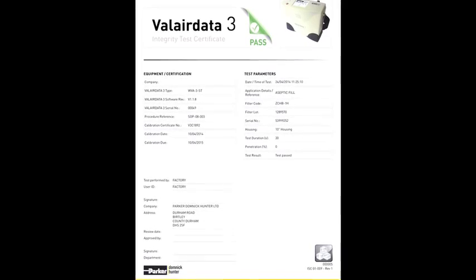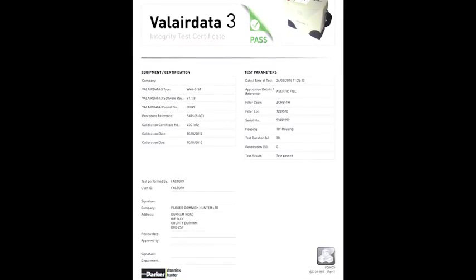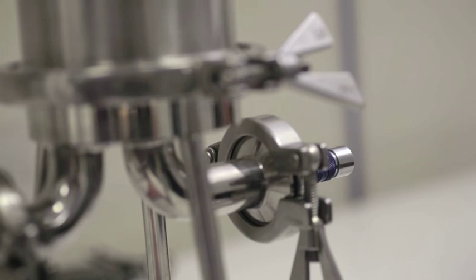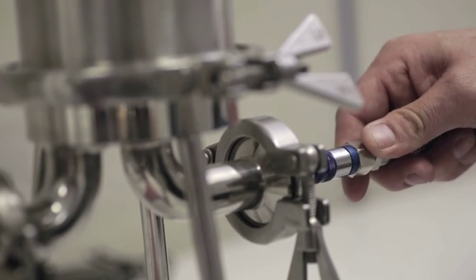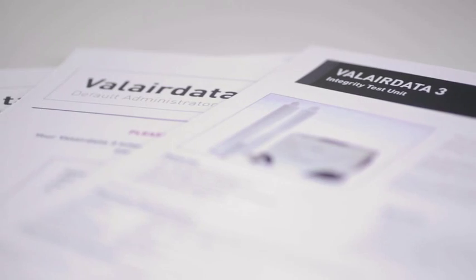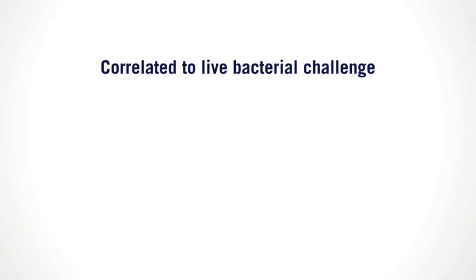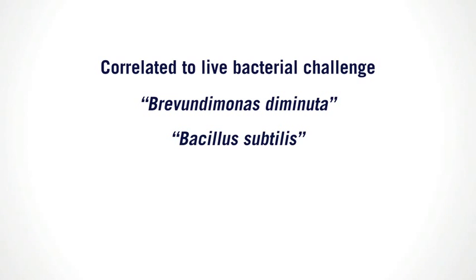A PASS certificate demonstrates a filter is fit for purpose and is capable of delivering sterile gas to protect the process from bacterial and phage contamination. The ValairData 3 test has been correlated against live aerosol microbiological challenges using Pseudomonas diminuta, Bacillus subtilis and MS2 coliphage organisms.